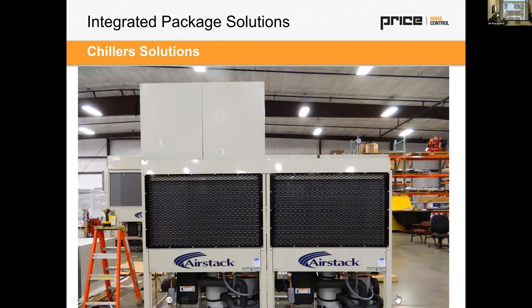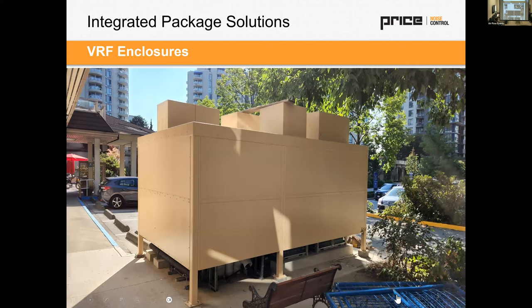Chillers are a big noise problem with condensing fans and compressors, and these are silencers mounted to the condensing fan section of a chiller. I've seen guys put blankets around the compressors. Is that worth its salt? They do work, but to limited effect. A blanket can only absorb so much. They're thin, mass-loaded vinyl products.